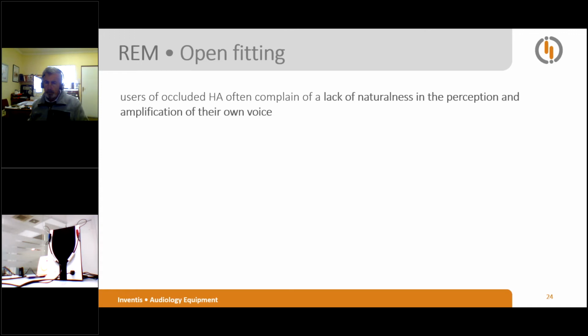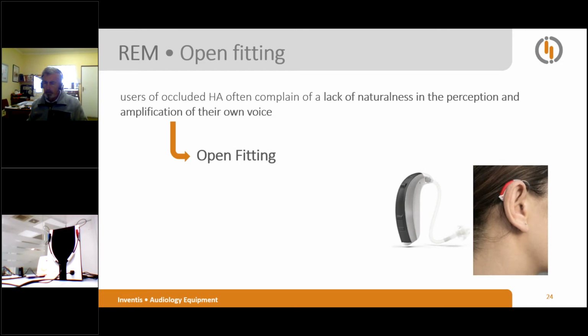Very important. The introduction of open fitting has allowed a great step forward in solving the problems related to comfort and satisfaction. This system allows almost complete communication between the outside and the inside of the ear canal. You know, the open hearing aid. I would say that it is suitable for patients suffering from high frequency hearing loss, with poor amplification needs at low frequencies. Instead of the tubing and the ear mold that occludes the ear, a fine plastic tube is used that ends with a soft cap that is inserted into the ear. You can see this picture on the screen.